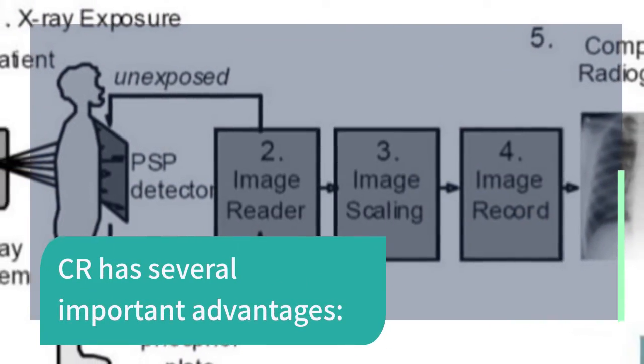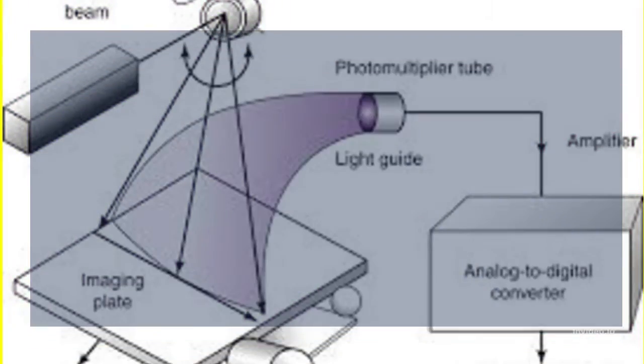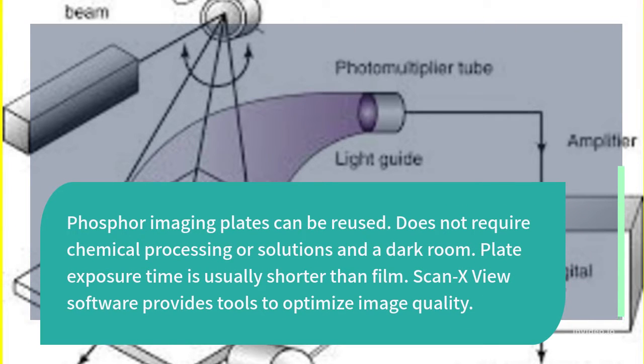CR has several important advantages. Phosphor imaging plates can be reused. It does not require chemical processing or solutions in a dark room. Plate exposure time is usually shorter than film. ScanX View software provides tools to optimize image quality.